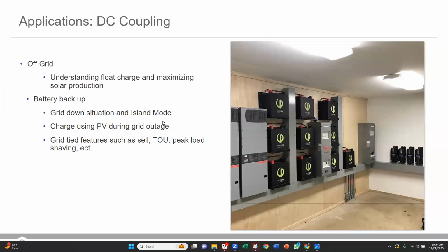Why are your battery systems configured for 48 volts? Wouldn't it be more efficient to use much higher battery voltages, not requiring a boost stage in your inverter? Absolutely. The reason is safety. For large scale systems, we do have high voltage offerings. We make batteries up to 1200 volts for our commercial and industrial purposes. But 48 volts is effectively the standard voltage for home batteries, and it has to do with safety.